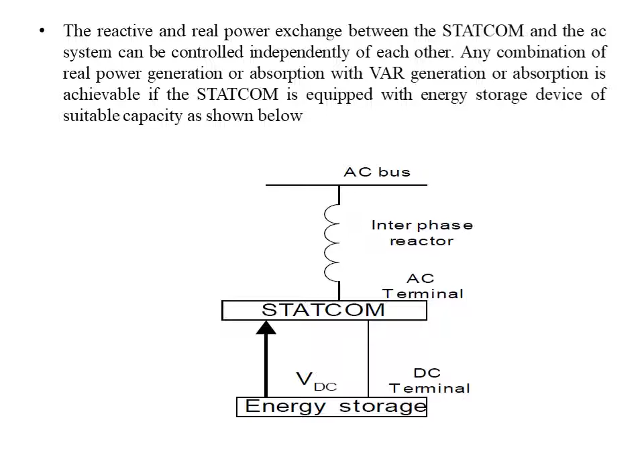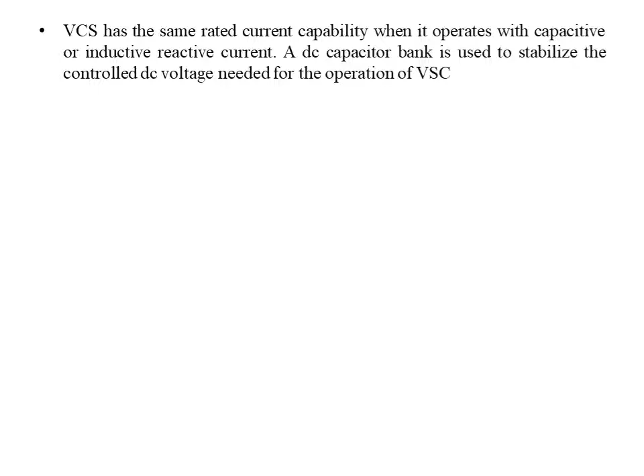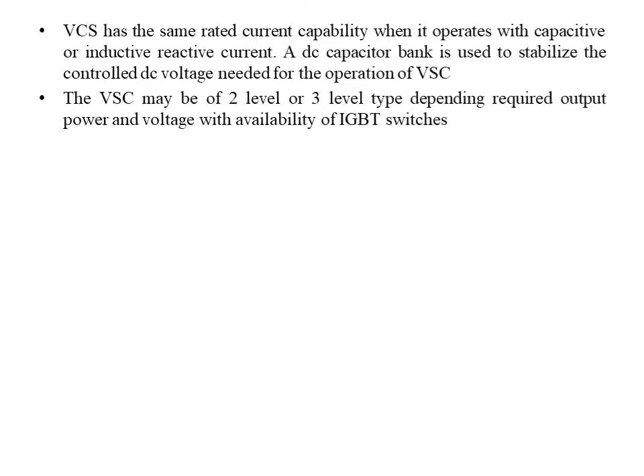The voltage source converter has the same rated current capability when it operates with capacitive or inductive reactive current. A DC capacitor bank is used to stabilize the controlled DC voltage needed for the operation of the voltage source converter. The voltage source converter may be two-level or three-level type depending upon the required output power and voltage, with availability of IGBT switches. Now we have the hybrid configurations of STATCOMs also. Multi-level STATCOMs are also available depending upon the output voltage required. So it may be 2 level, 3 level, 6 level, 12 level, and so on.